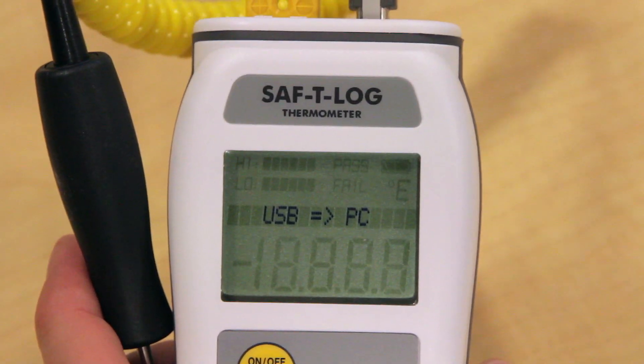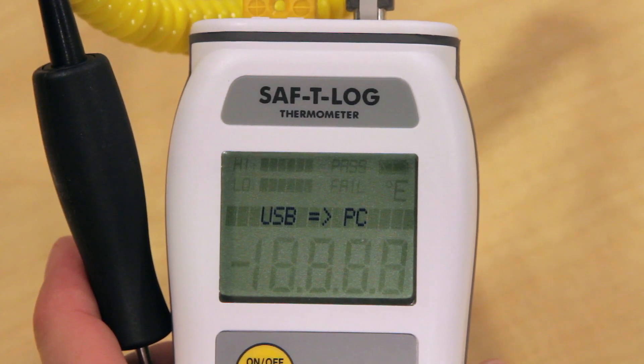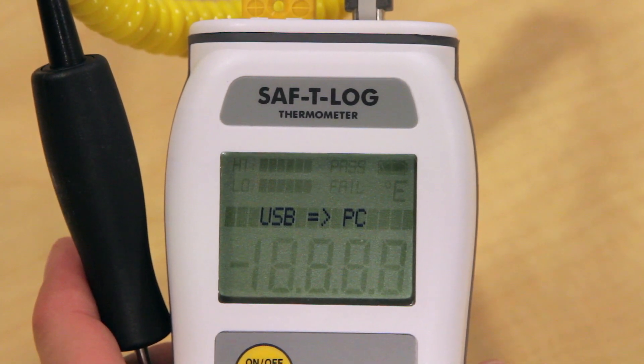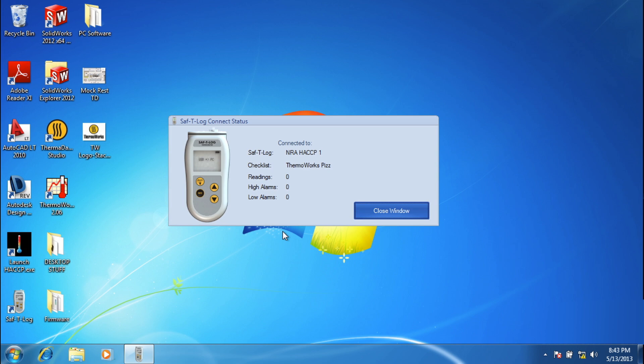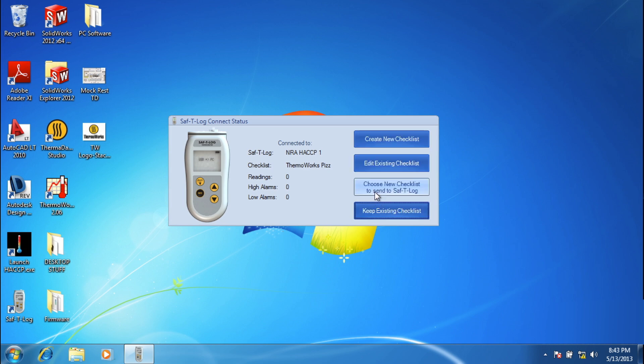With the checklist items loaded onto the handheld, attach the appropriate Type-K thermocouple probe and begin storing readings with the push of a button.